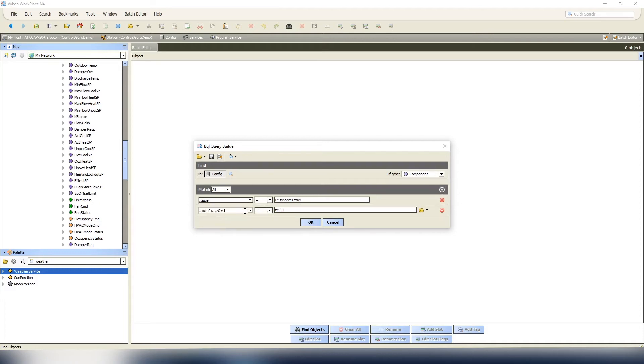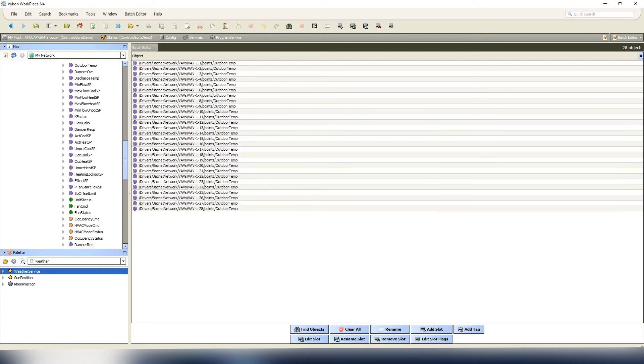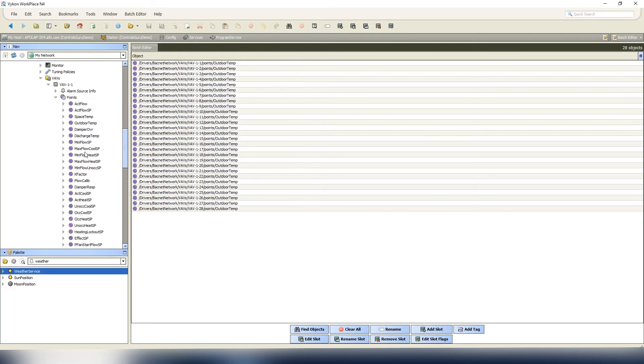We want to be a little bit more specific in case we use the same naming nomenclature. So we will do parent dot parent dot display name, because that's our VAV folder. It's gonna be like, and we're gonna make sure we look for VAV star. Here we go - it has found the outdoor temp for all of our VAV controllers.